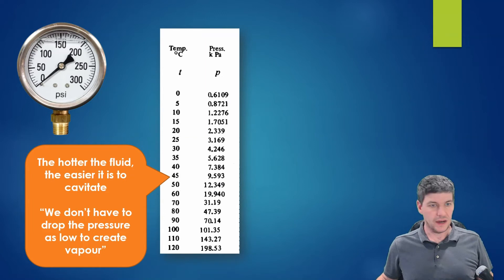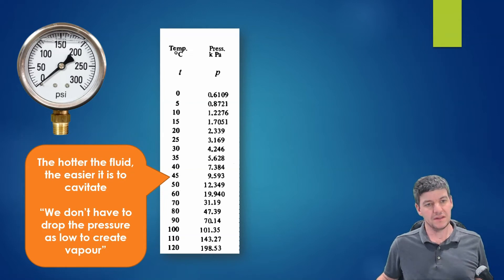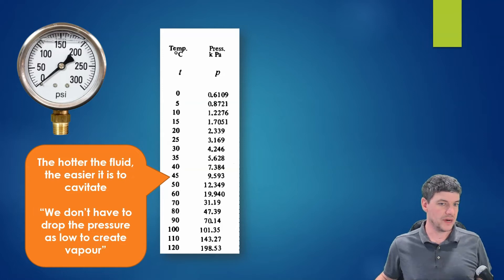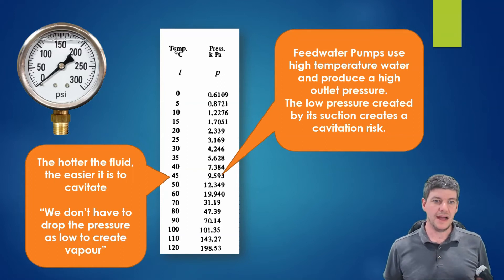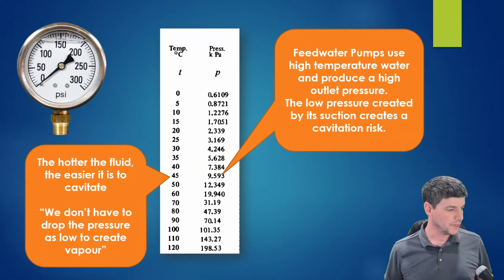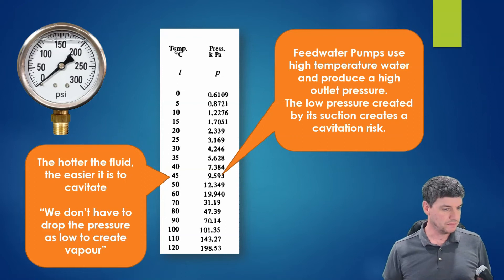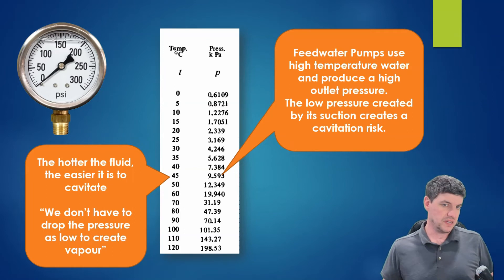The hotter the fluid, the easier it is to cavitate — we don't have to drop the pressure as much to create vapor, because hotter fluid evaporates at a higher pressure. A feedwater pump is a good example: preheated feed water is at high temperature and the pump must produce high pressures to overcome boiler pressure. These two factors combined put a feedwater pump at high risk of cavitation.